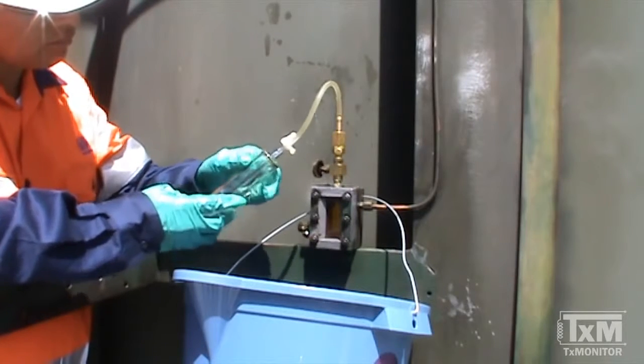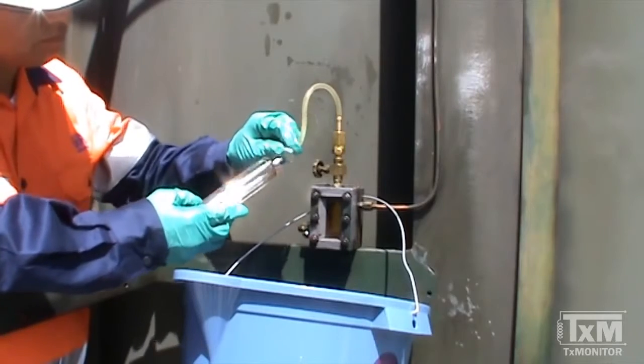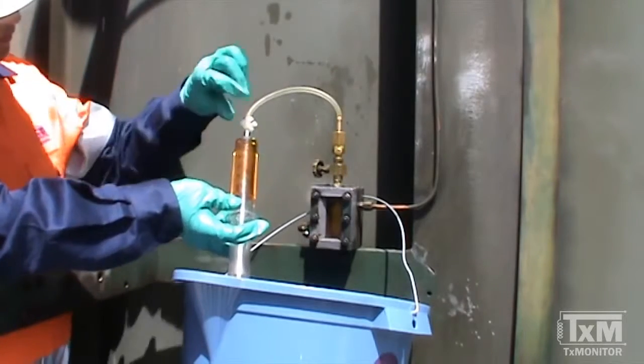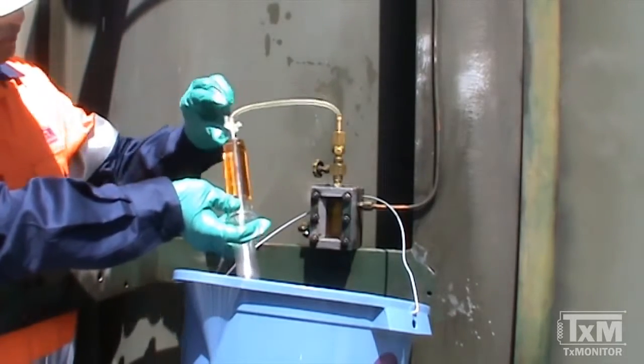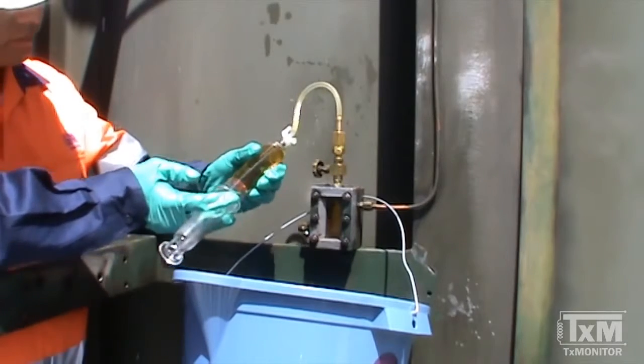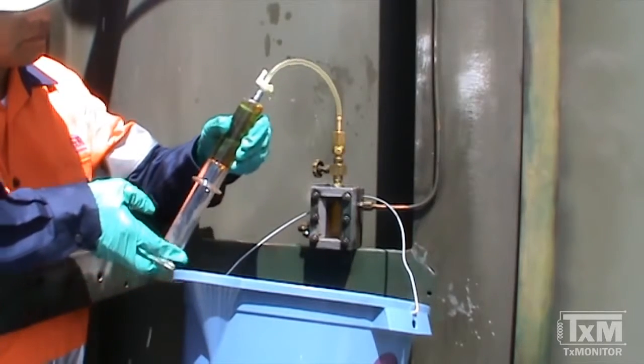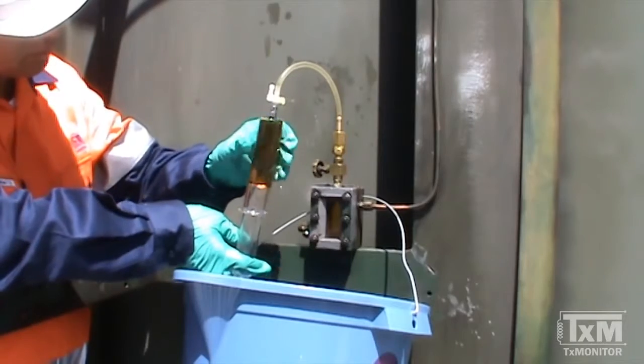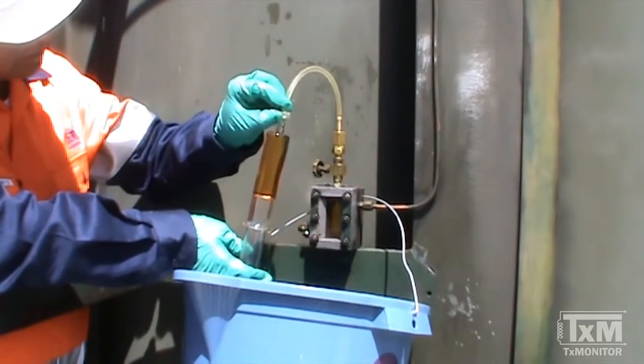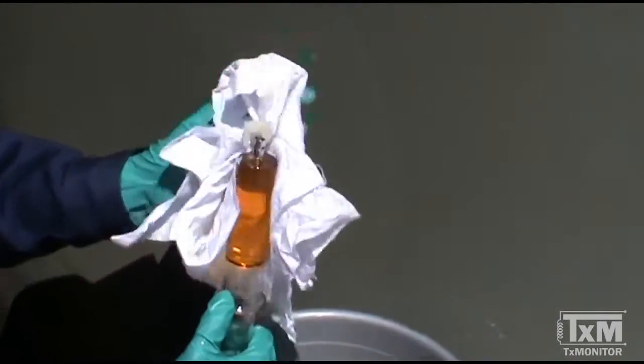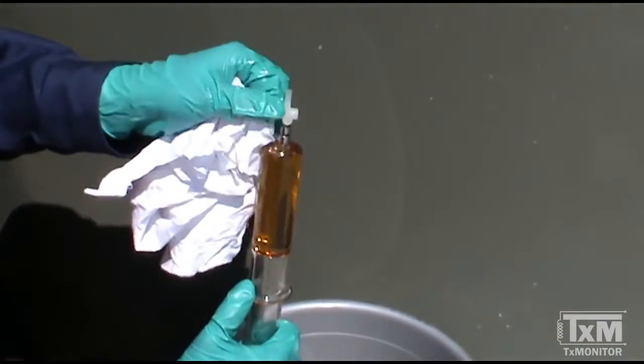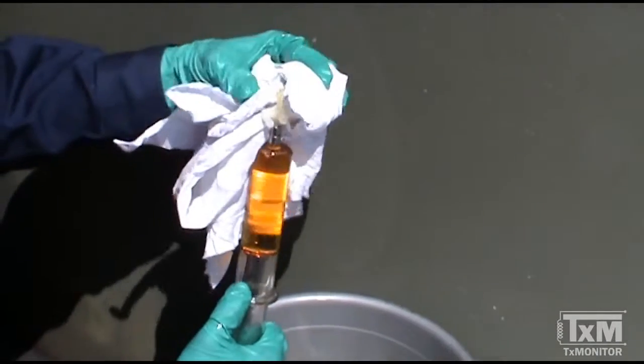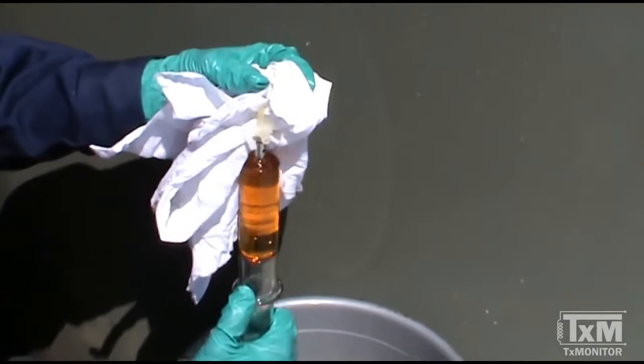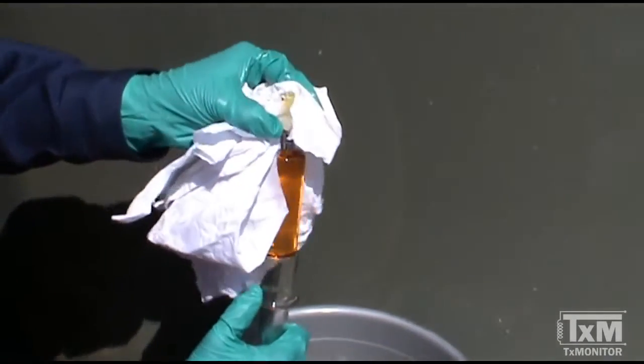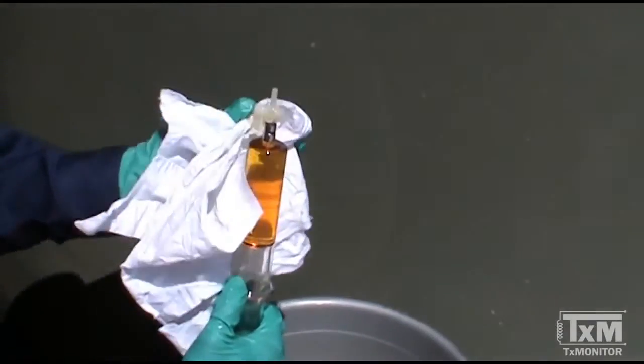Allow 50 milliliters to enter the syringe, then immediately close the port to the syringe by turning the handle to position 1. Hold the syringe vertically, keeping the handle in the closed position. Move the stopcock to position 2 and eject any bubbles by carefully depressing the plunger. Turn the stopcock to the closed position, which is position 1.